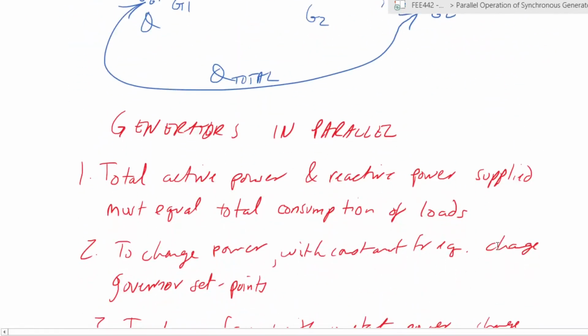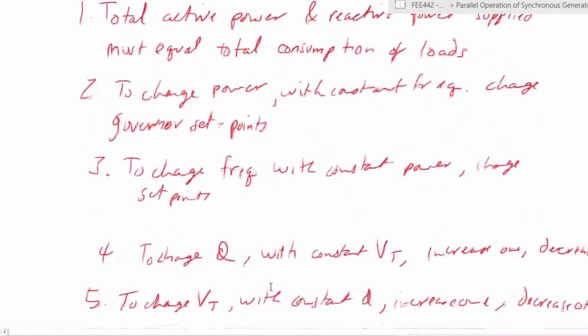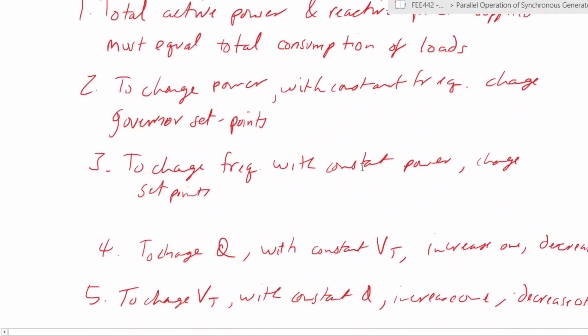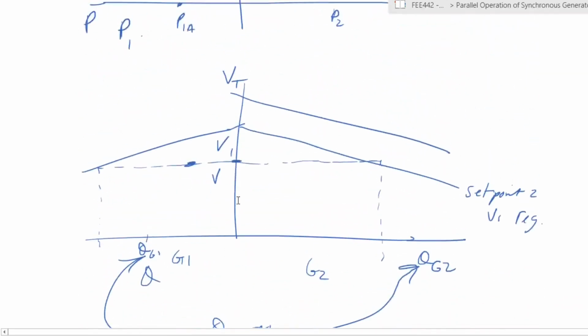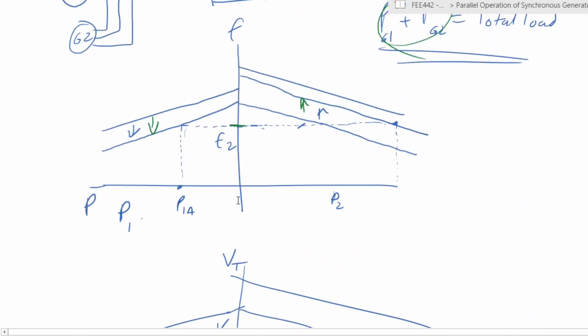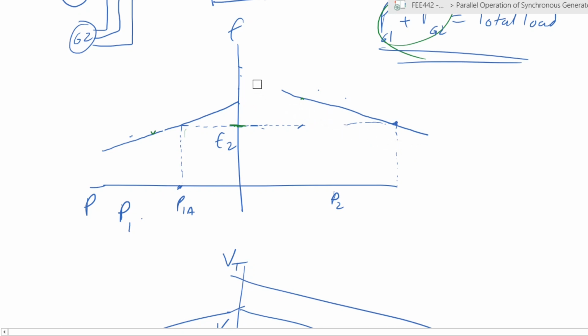To change the power with constant frequency, change the governor set points, as we've indicated. Increase one and decrease the other. This other one, to change the frequency with constant power, we have to also change the set points. So let's look at how those set points will look like. So let's say you have your F2 here, and we want to then change it. So let's remain with only the values that we are looking at. Clean it up a bit. So let's say P2 is here. Let's simplify the diagram a bit.